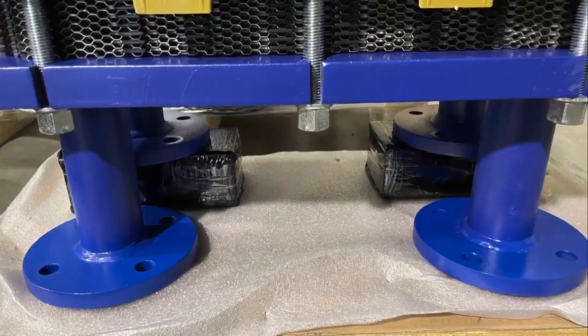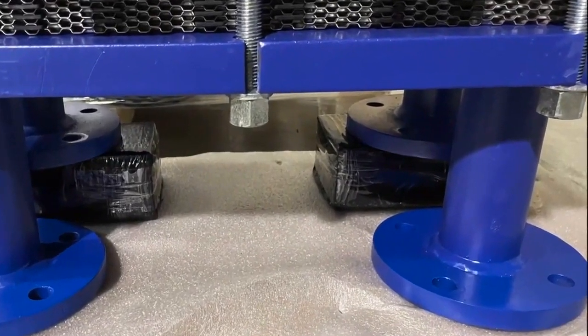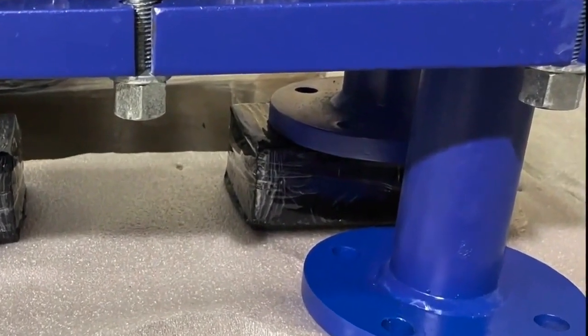It varies depending on how we choose to construct the plate heat exchanger, and what occurs in reality. If we have fluids that have no problem being in contact with carbon steel, as you can see from these photos, the fluid, when it enters the flange, is in contact with carbon steel, then it comes into contact with the plates, which are made of stainless steel.